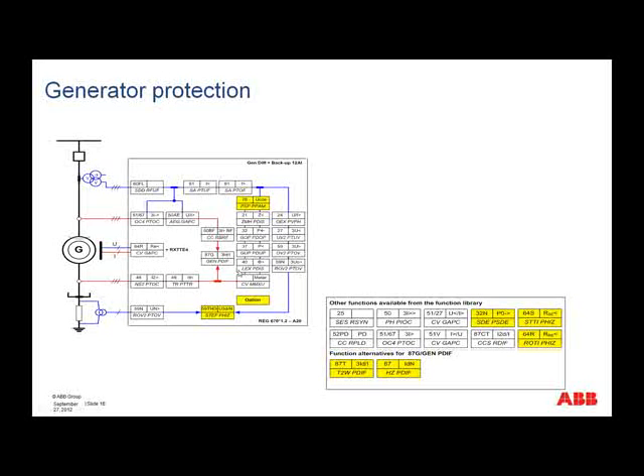And then there are also other functions that we would want to include for the metering or more measurements, I guess you could say. And there we'd be looking at measurement for display purposes of current, voltage, megawatts, megavars, etc. Then, of course, there may be other functions that would be required, maybe instantaneous overcurrent, maybe pole discrepancy, maybe voltage-dependent overcurrent. And together, all of these functions would then make up your overall protection scheme to protect the generator.